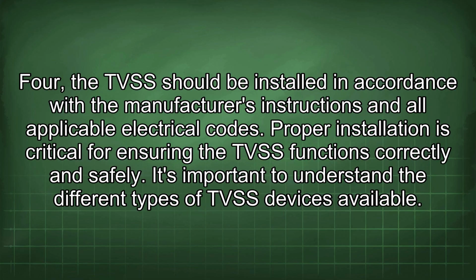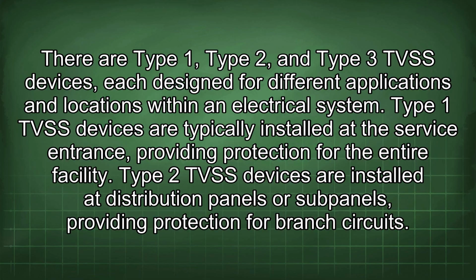4. The TVSS should be installed in accordance with the manufacturer's instructions and all applicable electrical codes. Proper installation is critical for ensuring the TVSS functions correctly and safely. It's important to understand the different types of TVSS devices available. There are Type 1, Type 2, and Type 3 TVSS devices, each designed for different applications and locations within an electrical system. Type 1 TVSS devices are typically installed at the service entrance, providing protection for the entire facility.